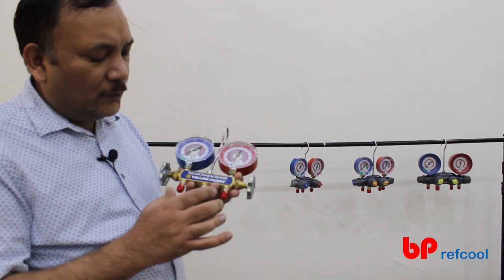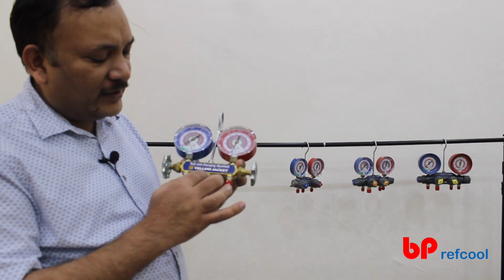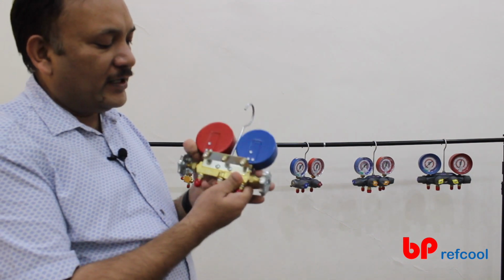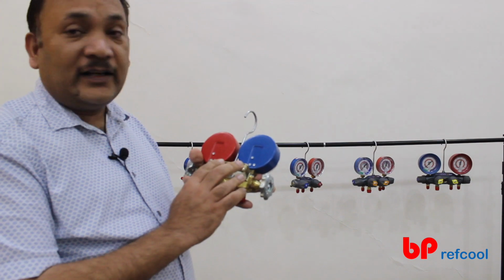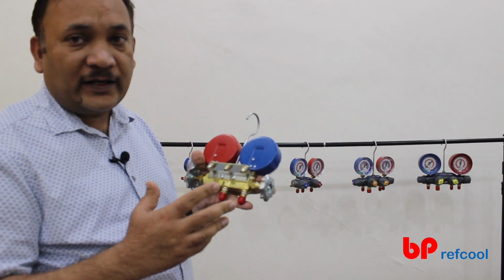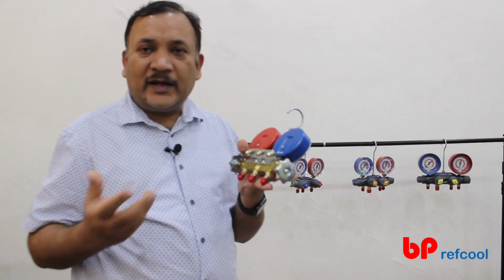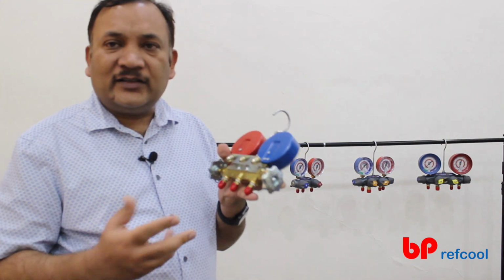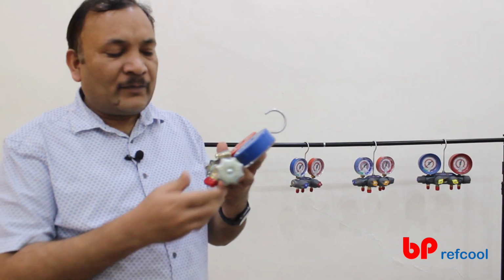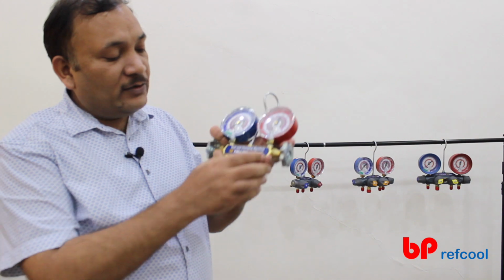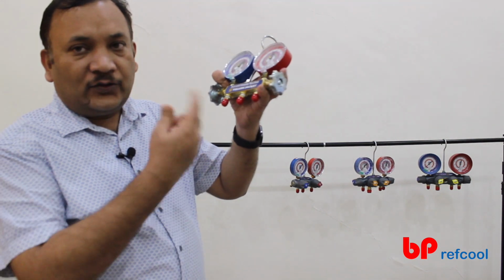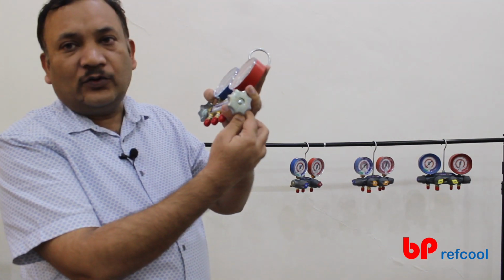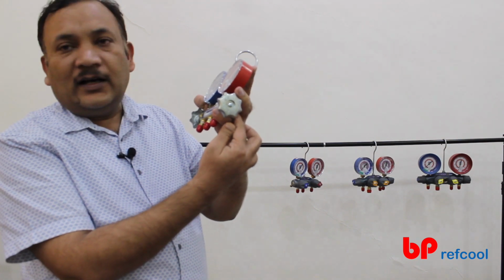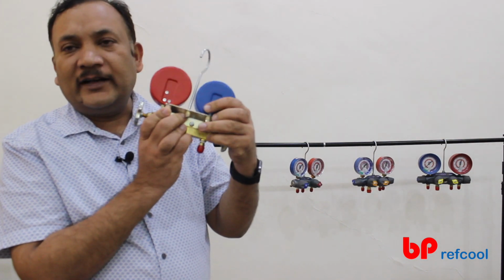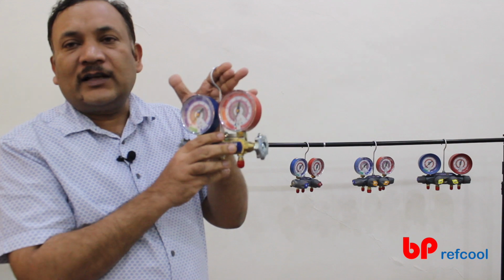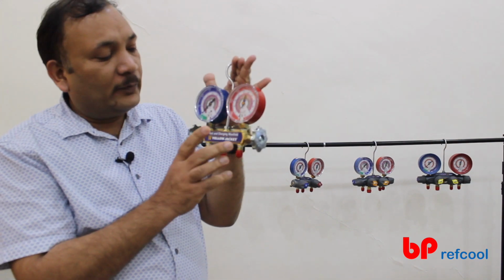In a two-way manifold gauge, you will see there are three connections at the bottom and three connections at the back. The three connections at the back are dummy connections, so they don't make any actual connection. They are just to hold the hoses. When you have these hoses lying here, you can connect the other end of the hoses onto the back of the manifold gauge, just to secure them after the job is done.